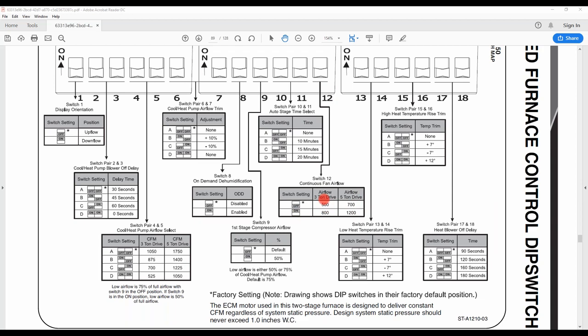If you use the Econet thermostat, Econet takes over and it gives you 5 different setting options for that instead of 2. All right, switch number 13 and 14. 13 and 14 is going to be our low heat temperature rise. Comes factory set in the off position at a nominal temperature rise.